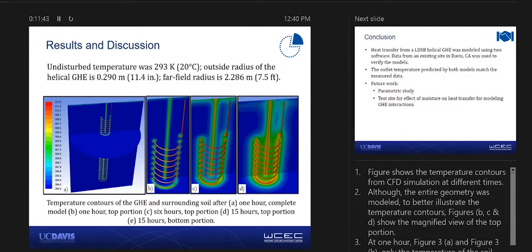This also answers a question some vendors have: do we go with highly expensive backfill that has good thermal conductivity? Does that significantly increase performance? The answer is yes and no. Yes, it increases performance in the short term, so if you have cyclic loads, that's a good thing. But if you're dumping heat over a long period of time, the backfill will get saturated with heat, and after that it's up to the soil to dissipate it.